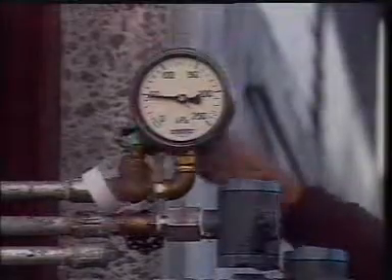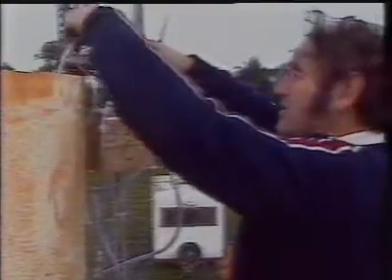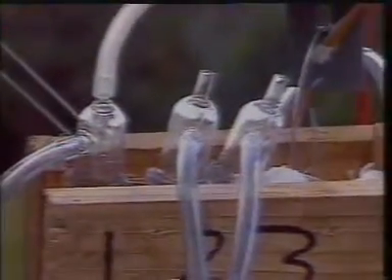It was then filmed with a normal video camera until the smoke, which filled the area within minutes, made this impossible. From then on, an infrared video camera recorded each test. As you will see later, it provided the clearest record, even though the pictures are in black and white. This camera was able to trace the progress of the fire. As well as visual monitoring, air and steel temperatures were measured using thermocouples welded to the steel members. The pressure of the water at various points in the sprinkler system was also checked, as well as the smoke level through smoke meters. The concentration of toxic products was also monitored, as was the airflow in the building.